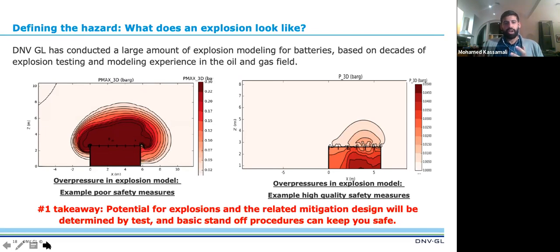So, you want to understand the gas dispersion within a given enclosure. As more gas is released within a closed space, the potential for an explosion or flammable environment changes, moving from a place of increasing volume of non-flammable gas to the lower flammability limit, and then to the upper flammability limit, where you're oxygen depleted, and the introduction of oxygen could lead to an explosive environment.